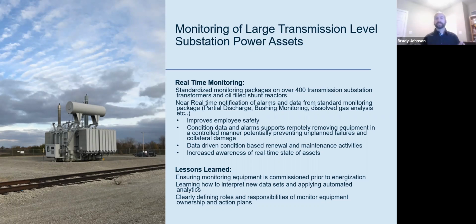We're extending those durations based on whether you have multiple gas units looking at the same thing, doing that check and balance, so you feel safe enough to justify why, instead of doing something every 6 months, we can push it out to every year — because we've got real-time data coming in, alarms, and other folks making those decisions based on that data.